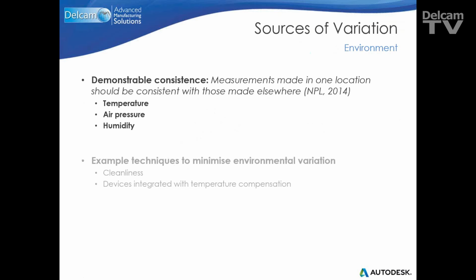If we have a dial test indicator, a 1 micron dial test indicator on a gauge block pile, and a lorry drives past in the roadway next to your building, you can actually see the needle quiver on the dial test indicator — that's vibration coming up through the floor and being fed right the way through to your sensor, your measuring device, in this case the dial test indicator.